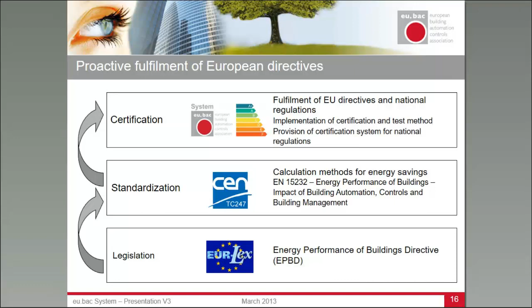This methodology is actually based on a standard as well, which in turn is based on the European legislation, the EPBD. Based on that EPBD, the industry together with CEN developed the EN 15232 standard, Energy Performance of Buildings, Impact of Building Automation, Controls and Building Management, the calculation method. In this standard we find functionalities defined that have to be implemented to achieve a certain level of energy efficiency in the building, and based on this standard we have developed this certification scheme.